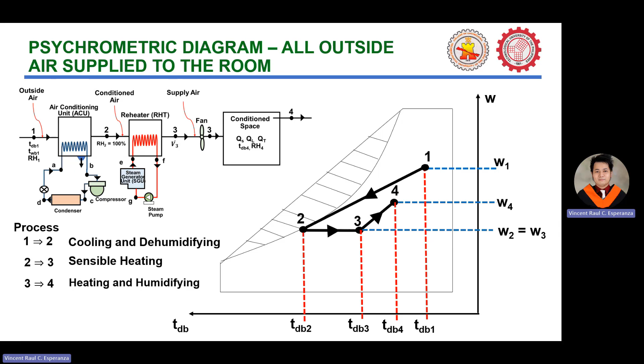And this is the problem in a space. Ito yung ating sample problem for all outside air supply in a space. The sensible and latent heat loads are 135 kilowatts and 34 kilowatts respectively. Outside air is at 32°C and 45% RH. The space is to be maintained at 25°C dry bulb and 18°C wet bulb temperature. All outside air is supplied with a reheater to satisfy the space conditions. The conditioned air leaves the supply fan at 17°C. Determine the following. So, napakaraming hinihingi. Okay? So, we have the refrigeration load, the fan capacity, ang dami-dami. Again, I think dito na tayo sa PowerPoint and mag-transfer tayo sa OneNote.